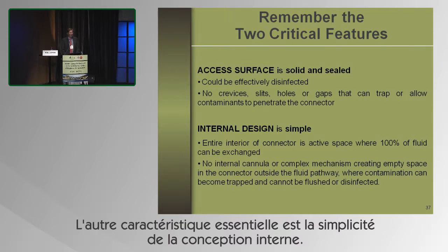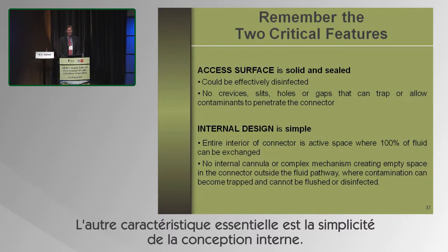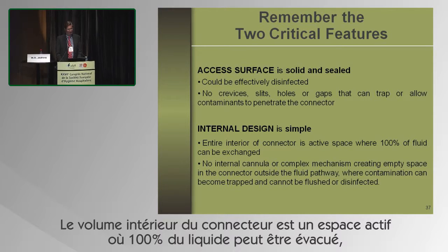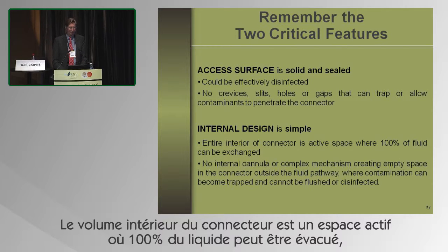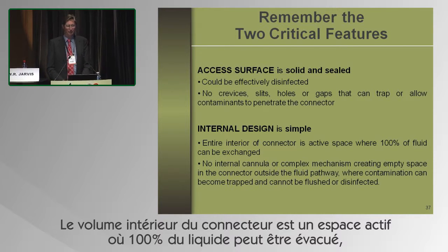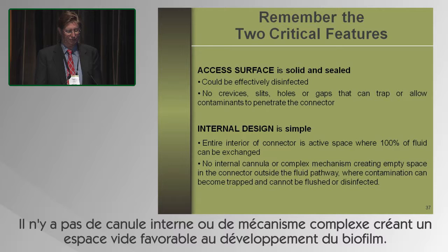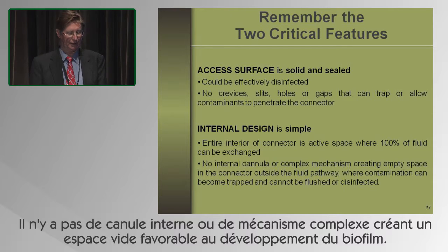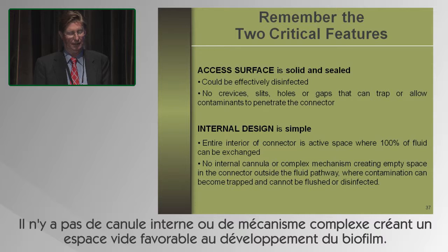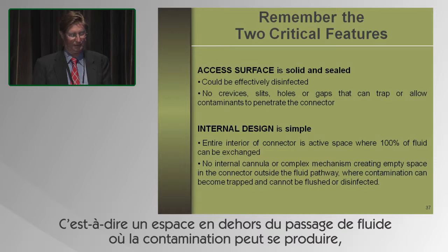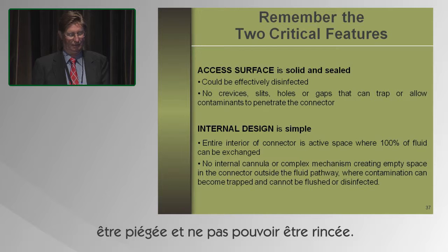And then secondly, is the internal design simple? The entire interior of the connector is active space where 100% of fluid can be exchanged. So it's being flushed each time it's used. And there are no internal cannula or complex mechanisms creating empty space or increased area for biofilm development that's outside the fluid pathway, where contamination can occur, become trapped, and you really can't flush it. And yet it can then re-enter the fluid path.